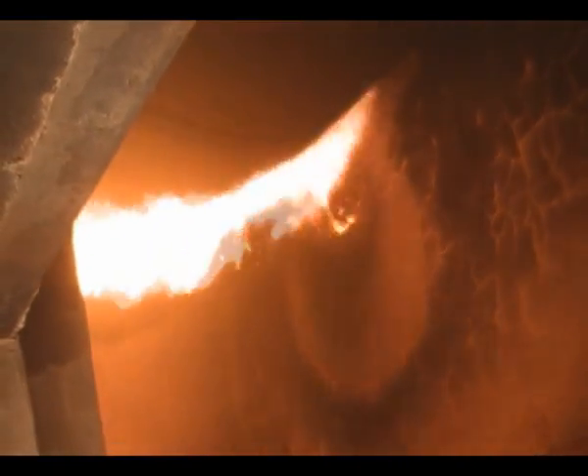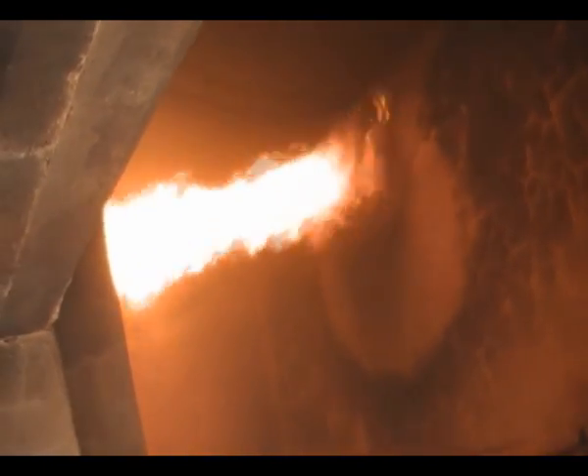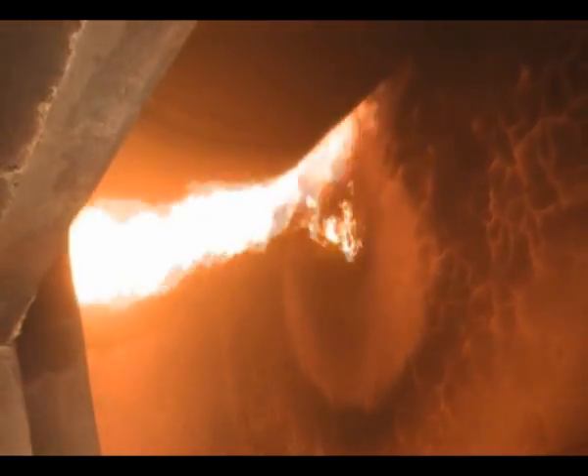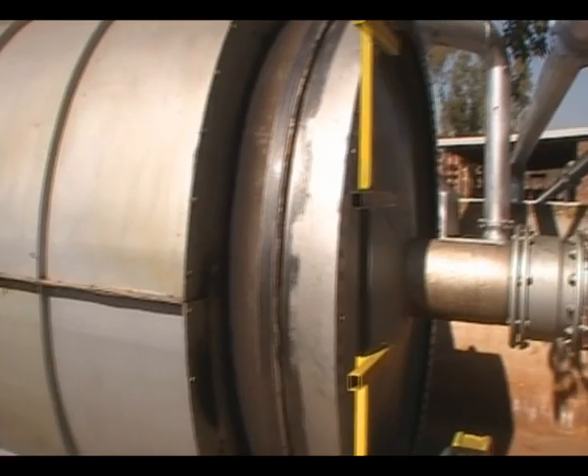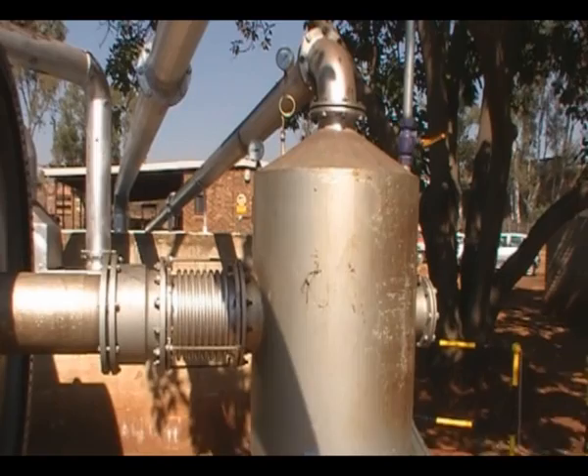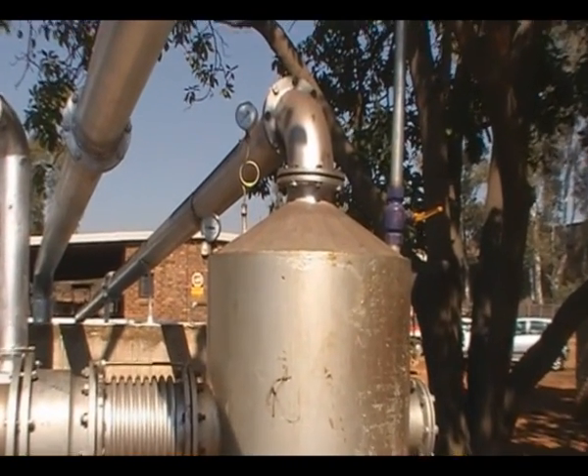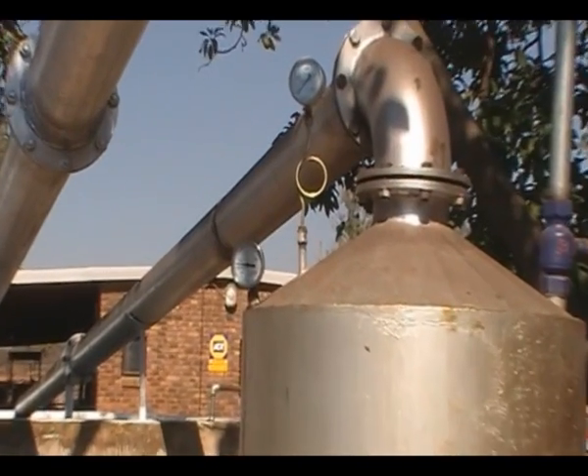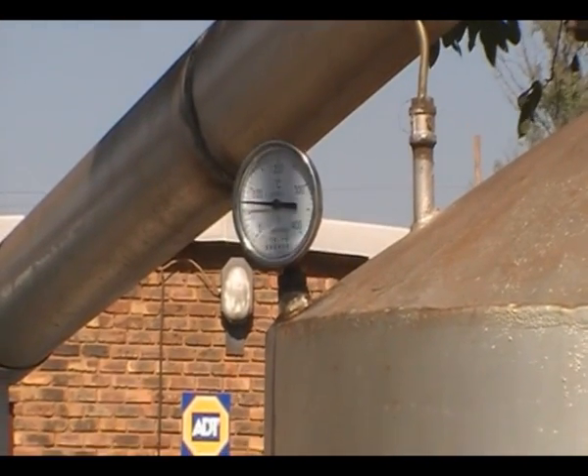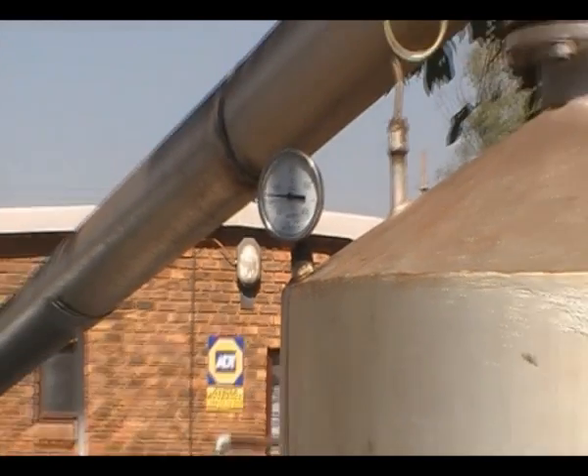This is the flame from one of the oil burners. You can clearly see how it goes around the whole reactor to start heating it up. By raising the temperature to about 300 degrees, the rubber starts gasifying and the gas moves through this pipe into the catchment tank and then over into the bigger pipes on the top to the cooling pond. The process is controlled by temperature and pressure.